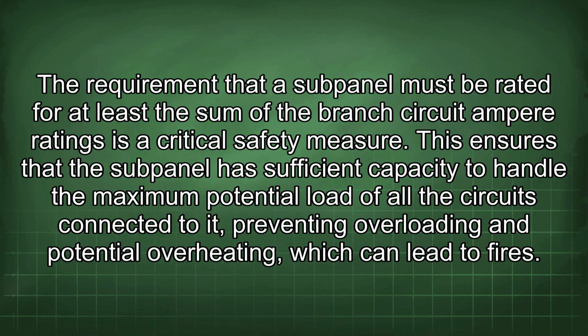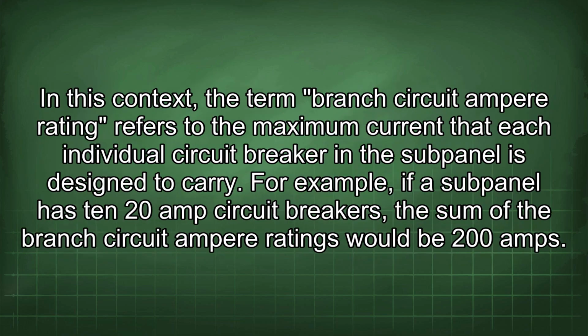The requirement that a subpanel must be rated for at least the sum of the branch circuit ampere ratings is a critical safety measure. This ensures that the subpanel has sufficient capacity to handle the maximum potential load of all the circuits connected to it, preventing overloading and potential overheating, which can lead to fires. In this context, the term branch circuit ampere rating refers to the maximum current that each individual circuit breaker in the subpanel is designed to carry.